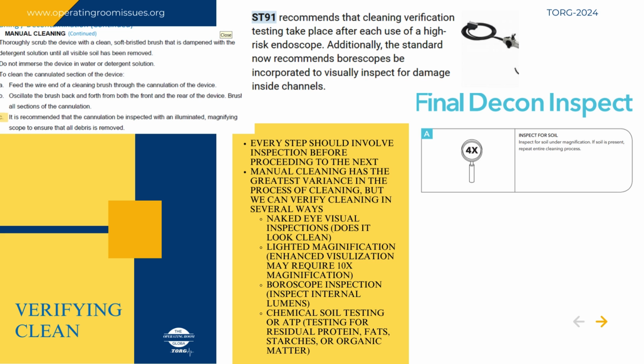ST91 is a guideline that we use in our standards that recommends that cleaning verification testing takes place after each use of high-risk endoscopes. Additionally, the standards now recommend borescopes be incorporated into visual inspection for damage inside of the channels. Again, without that technology, how do we know we're delivering safe items to the patient?